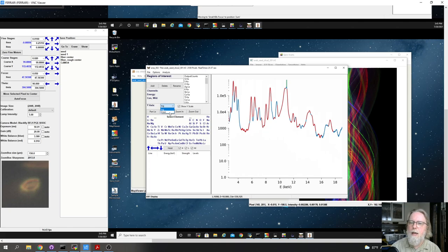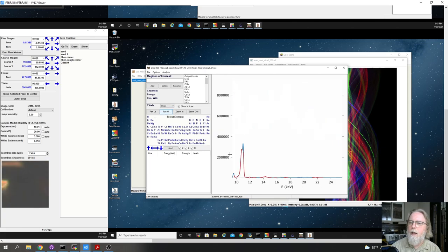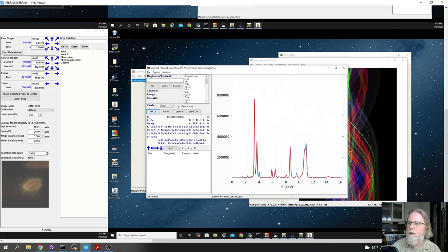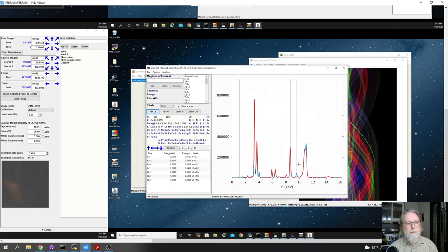We'll see those again. We'll see the Compton scattering. We'll see the zinc, some copper, some iron, manganese, and so on. We can go through the periodic table here and show all of the elements that are in the sample. So here we have, again, elastic, Compton, and zinc is predicted to be here. So there's a zinc K alpha and K beta emission. We're sending in 11 keV x-rays, and we're seeing zinc and lower concentrations.